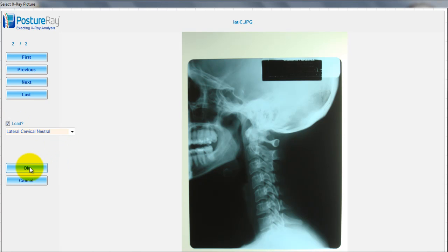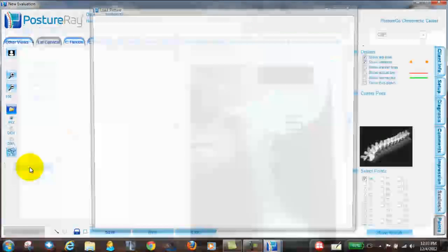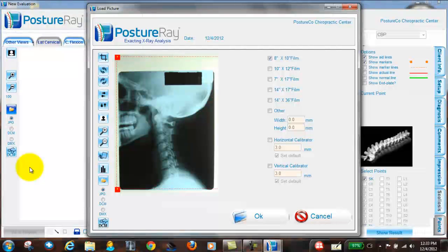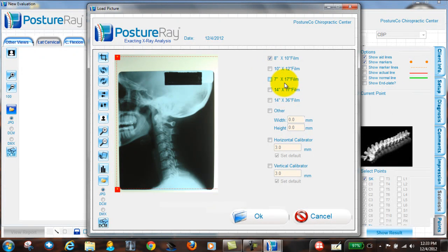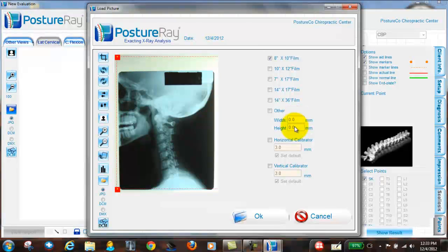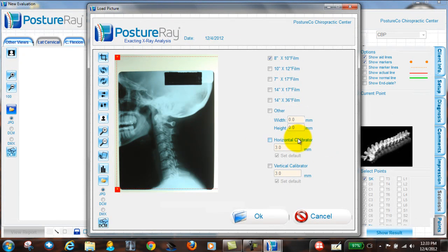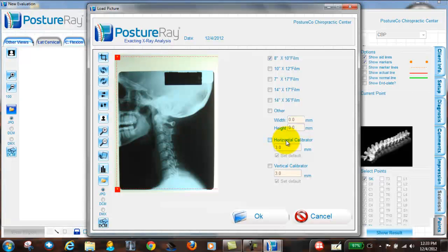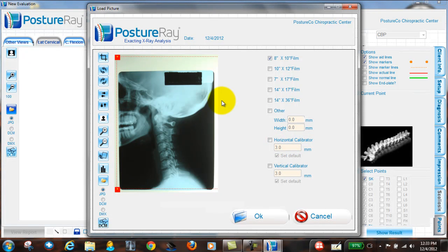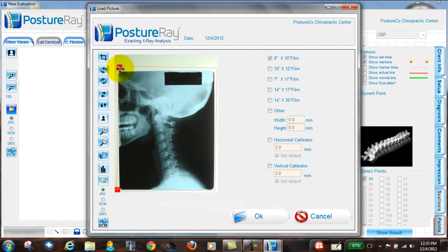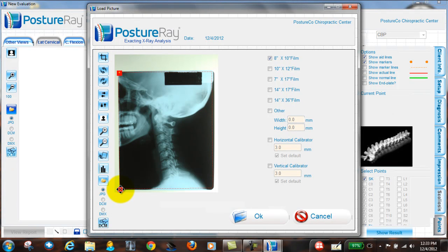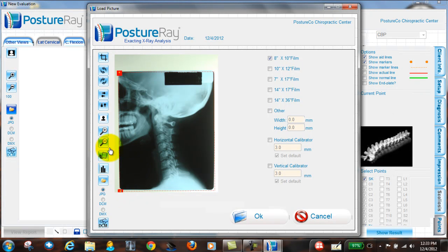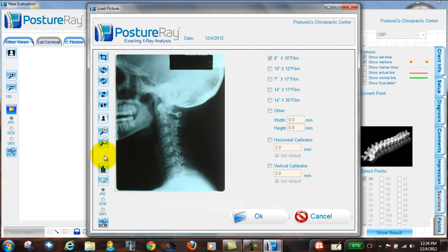Now, when we hit okay, we get a different, a slight alteration in the screen. At this point, we have to say, what size is the film, Doctor? Is it an 8x10, 10x12, 7x17, 14x17, 14x36, or do we want to put in our own millimeters measuring? I'll go into the secondary calibration at another training, but at this point, this is paramount that they do not make a mistake here. You must drag these points into place to fit around as best as you can around the full X-ray, and I'm going to come down just like that. And then we're going to click this guy right here. It's going to straighten and measure, and now we calibrated that to a known distance of an 8x10. So now it's accurate. We hit okay.